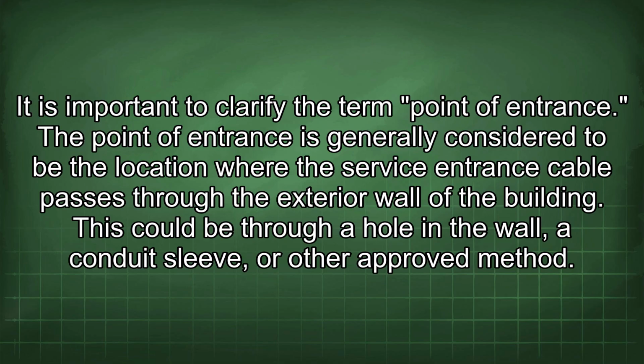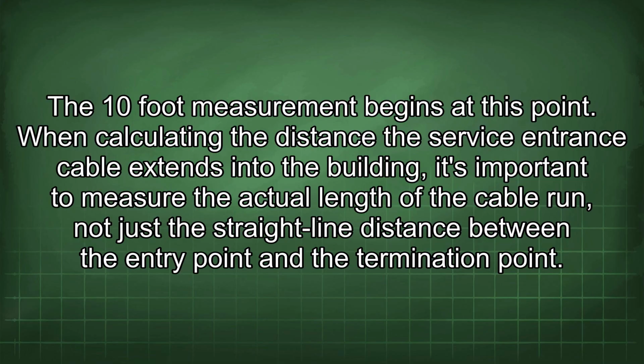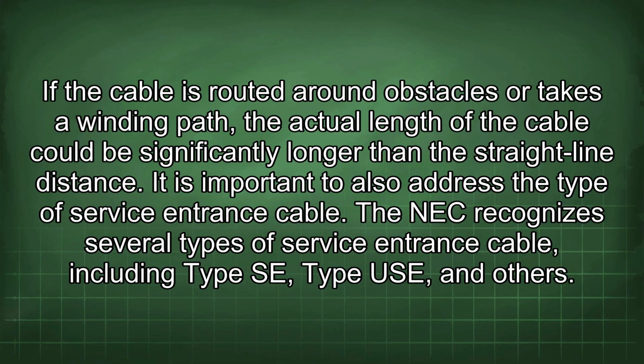It is important to clarify the term point of entrance. The point of entrance is generally considered to be the location where the service entrance cable passes through the exterior wall of the building. This could be through a hole in the wall, a conduit sleeve, or other approved method. The 10-foot measurement begins at this point. When calculating the distance the service entrance cable extends into the building, it's important to measure the actual length of the cable run, not just the straight line distance between the entry point and the termination point. If the cable is routed around obstacles or takes a winding path, the actual length of the cable could be significantly longer than the straight line distance.